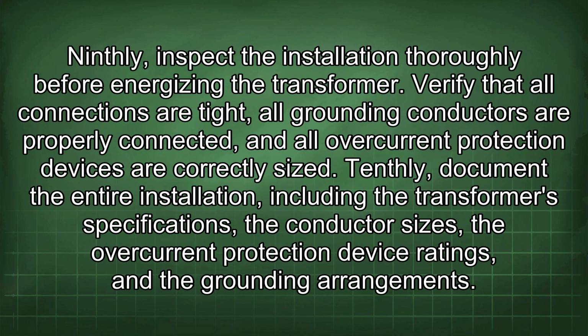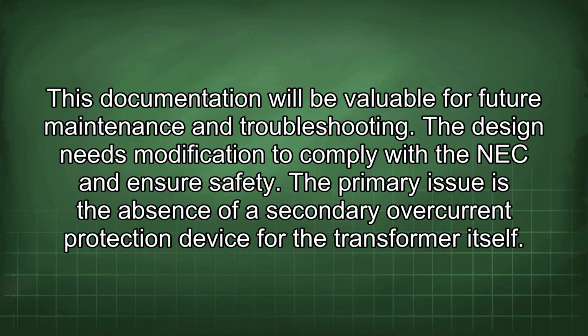Ninthly, inspect the installation thoroughly before energizing the transformer. Verify that all connections are tight, all grounding conductors are properly connected, and all overcurrent protection devices are correctly sized. Tenthly, document the entire installation, including the transformer specifications, the conductor sizes, the overcurrent protection device ratings, and the grounding arrangements. This documentation will be valuable for future maintenance and troubleshooting.